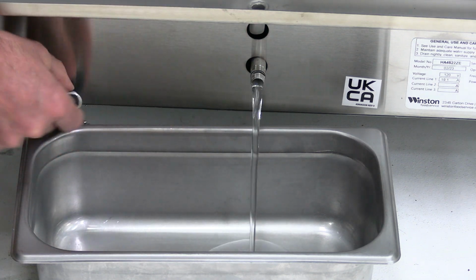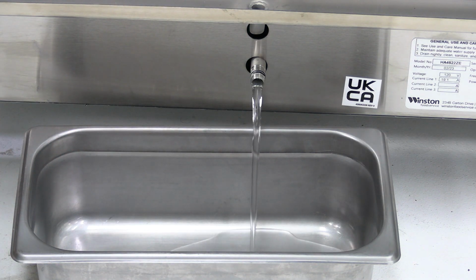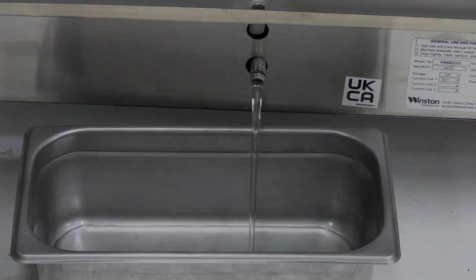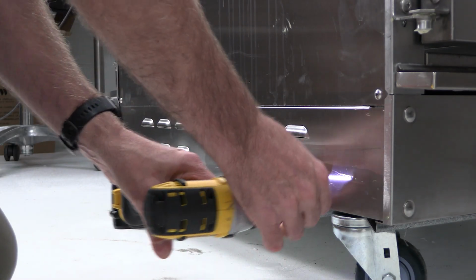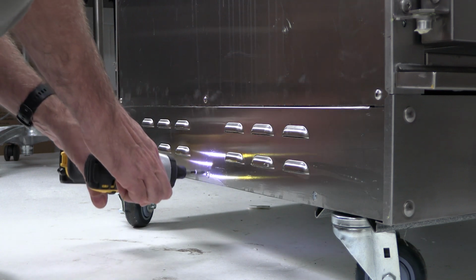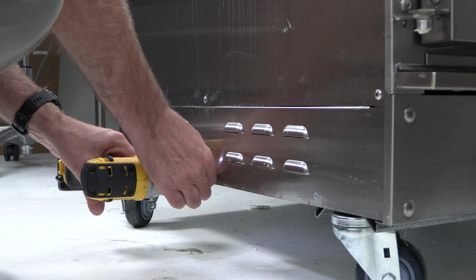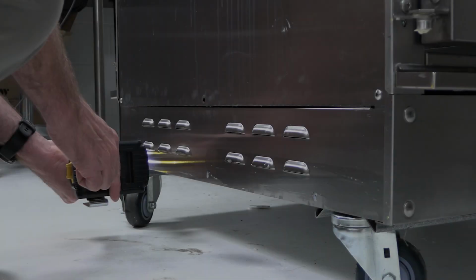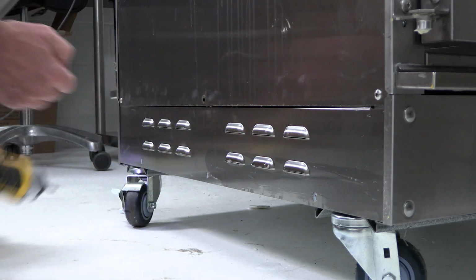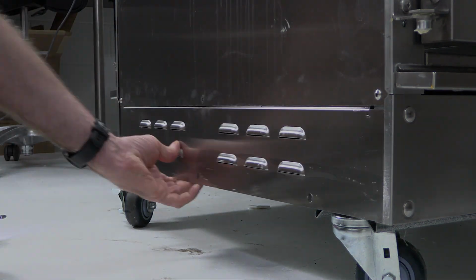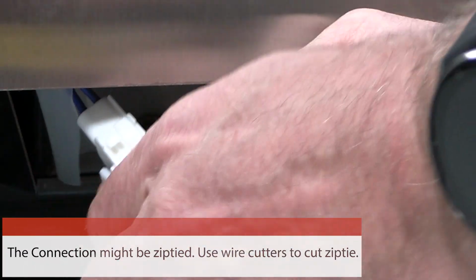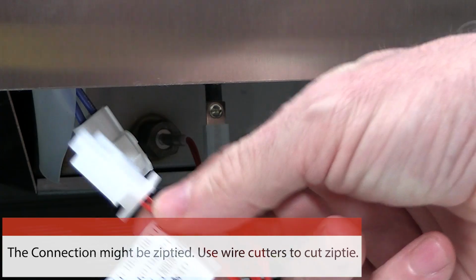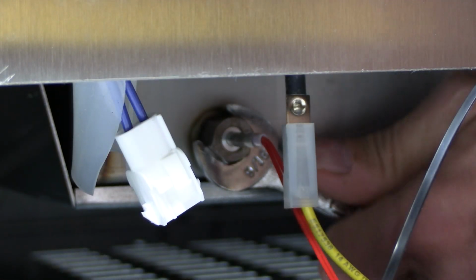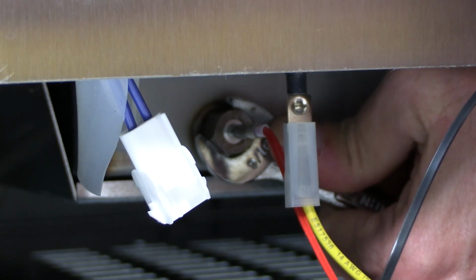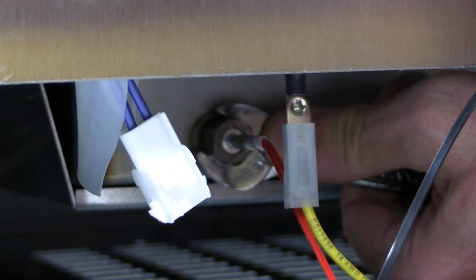Ensure that the evaporator pan is drained. Remove the lower right side access panel using a Phillips screwdriver or screw gun. Locate the water probe connection and then disconnect. Using a 9/16 inch wrench, remove the water probe compression nut.